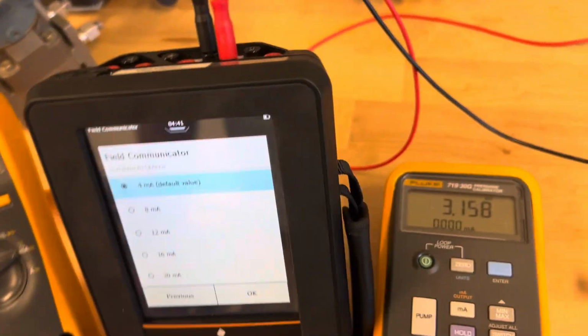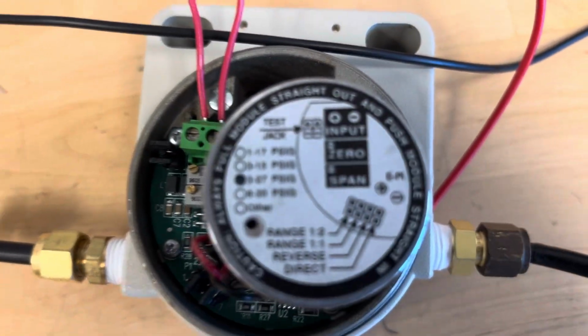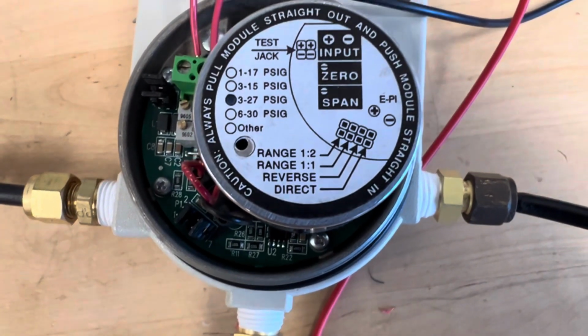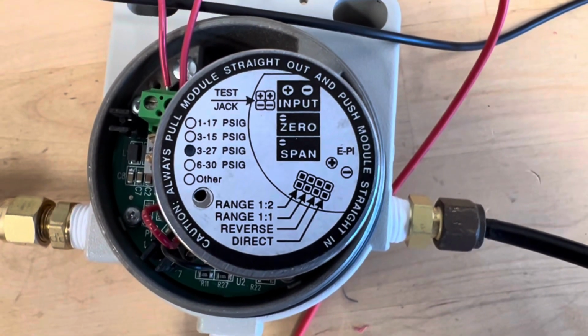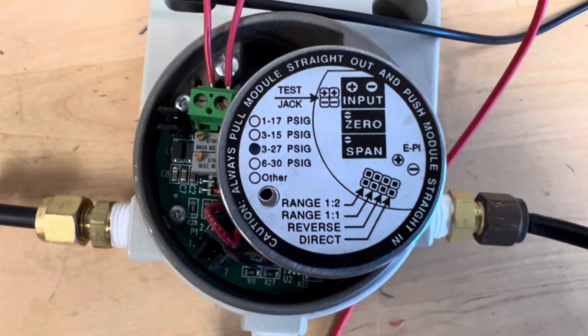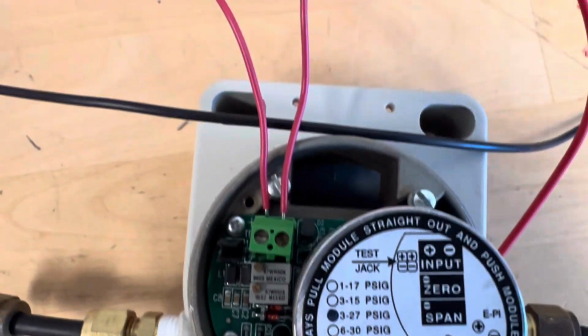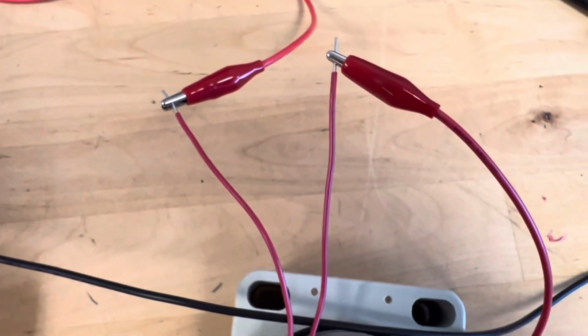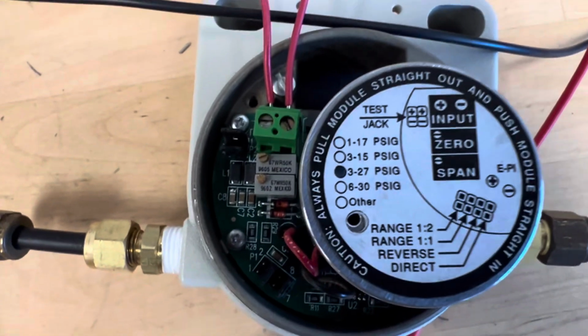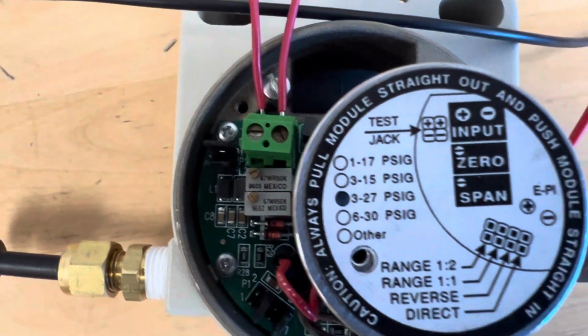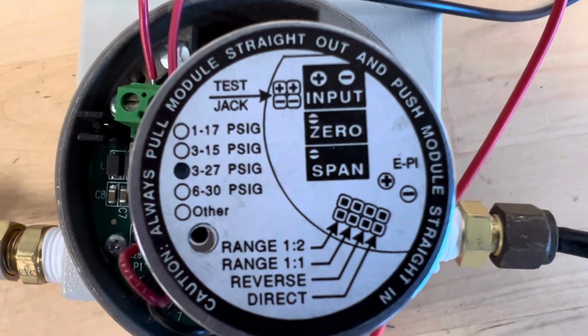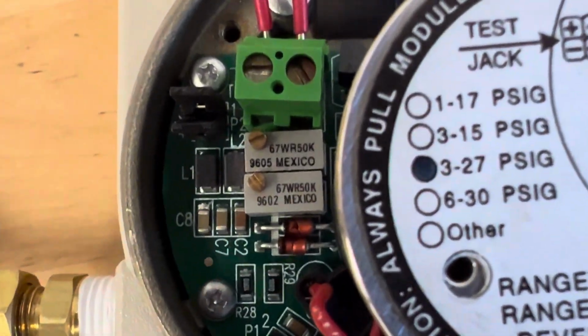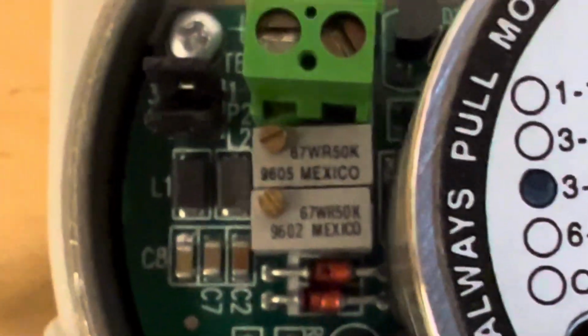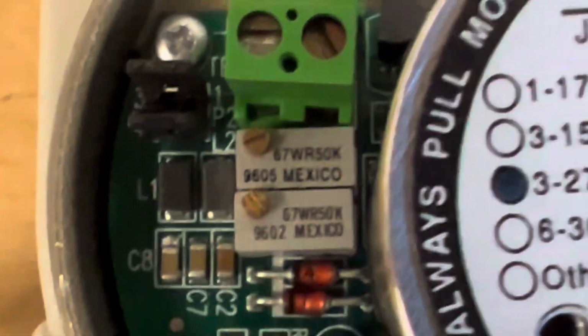Now, we're going to start by doing a zero and span calibration. So if we look here at the details on the transducer, it shows us first the input wiring, which are these 2 red wires here connected to the leads coming from my Trex. You've got your positive and your negative side. Then right below that, you have your zero span adjustment, which is this little potentiometer here, this little gray potentiometer. You see that screw on that potentiometer.